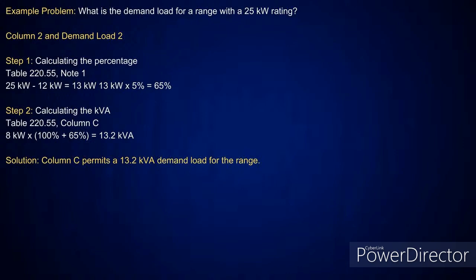It says, for ranges individually rated more than 12 kW, but not more than 27 kW, the maximum demand in column C shall be increased. Now listen to this, and you're going to see this a lot, so get used to this: 5% for each additional kilowatt rating. So if I take 25 kW, I'm going to subtract 12 because 12 is already taken up here, up to 12 kW in column C. That's going to give me 13 kW. Sorry, I should have moved that 13 kW down one. So I take the 13 kW, for each additional kilowatt, which is 5%, gives me 65%.